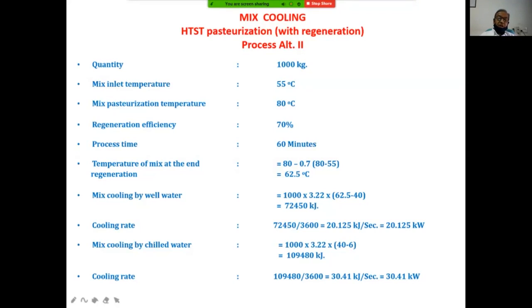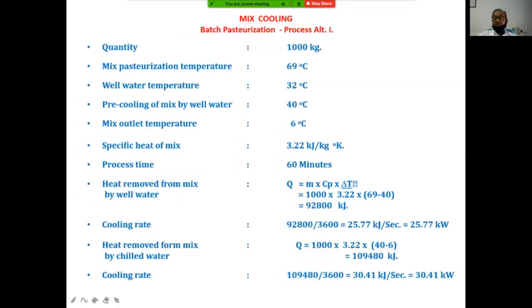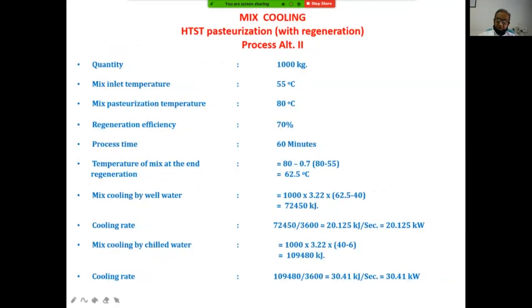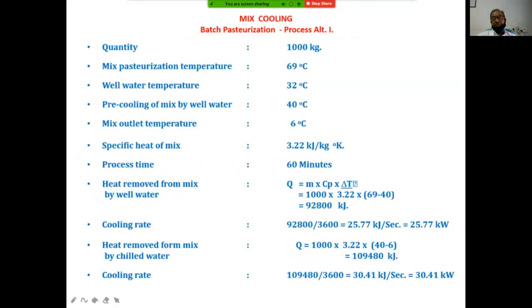So our mixed cooling load is 72,450 kilojoule. And if we make it in kilowatt, it's 20 kilowatt. Earlier, if you see the cooling load, it was 25.77 kilowatt, and it has been reduced to 20 point something by the HTST pasteurization process. But our cooling load on the chill water system or refrigeration system is 30.41 in this system, and in the same system you can see there is no change in refrigerant load.